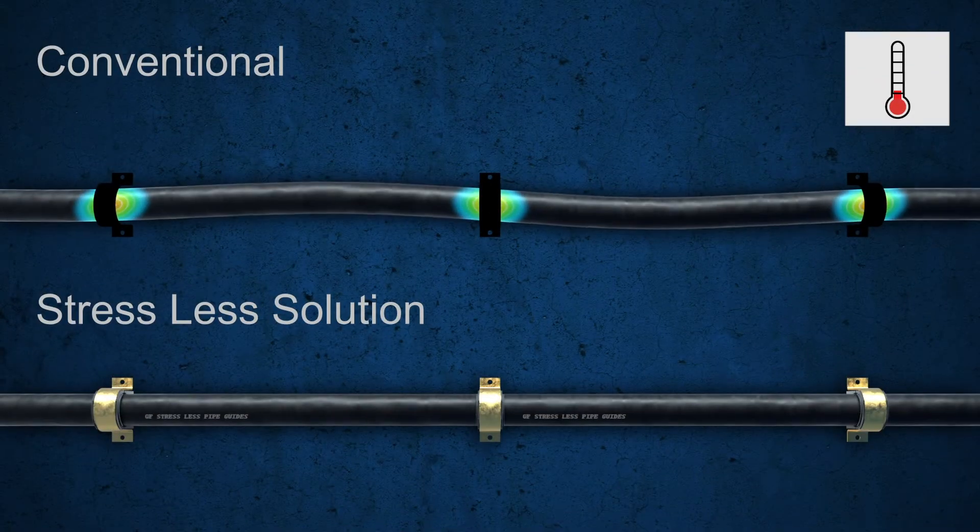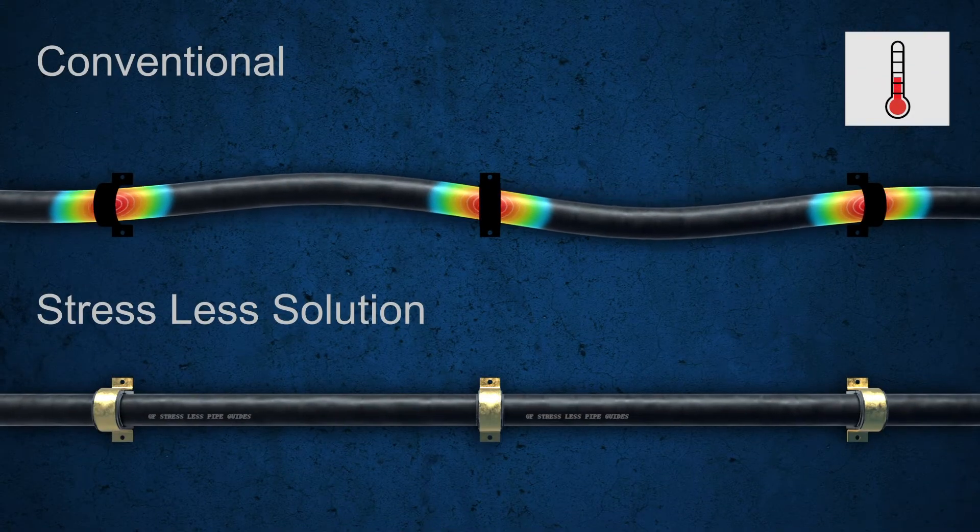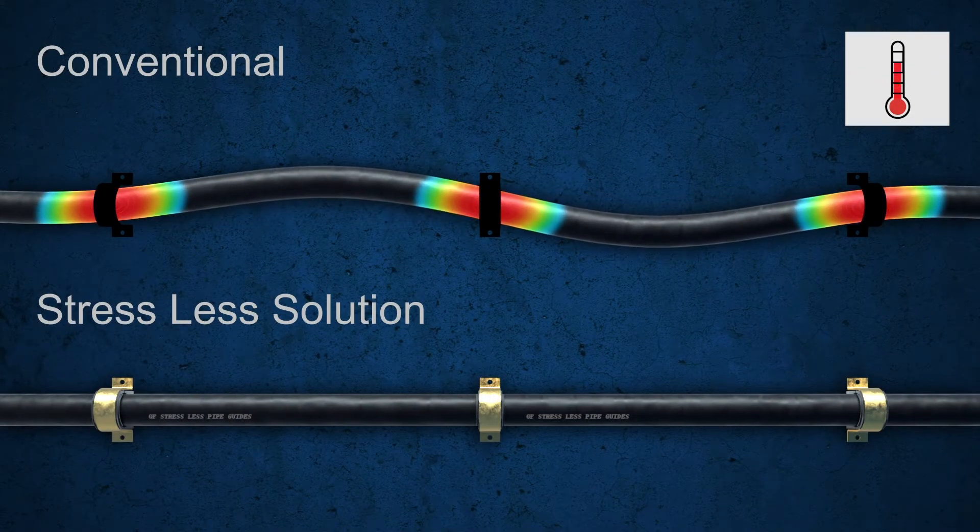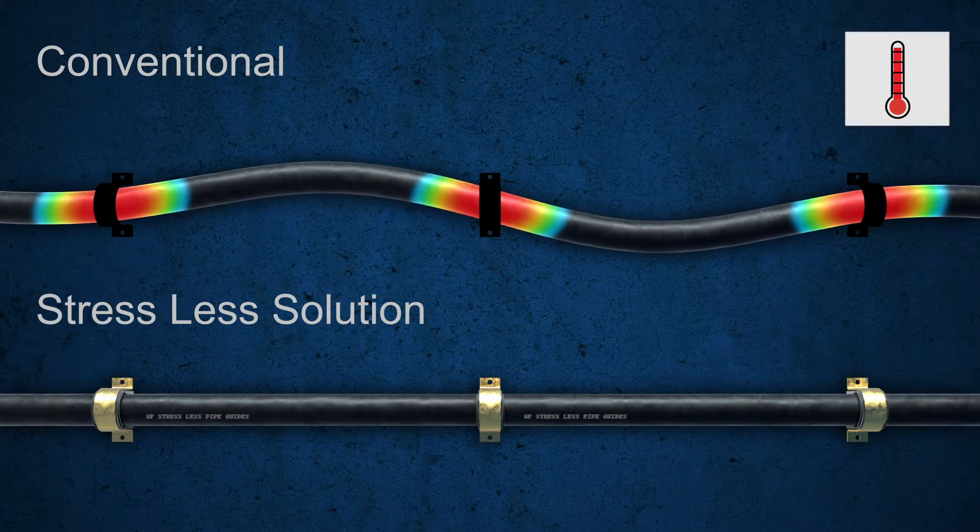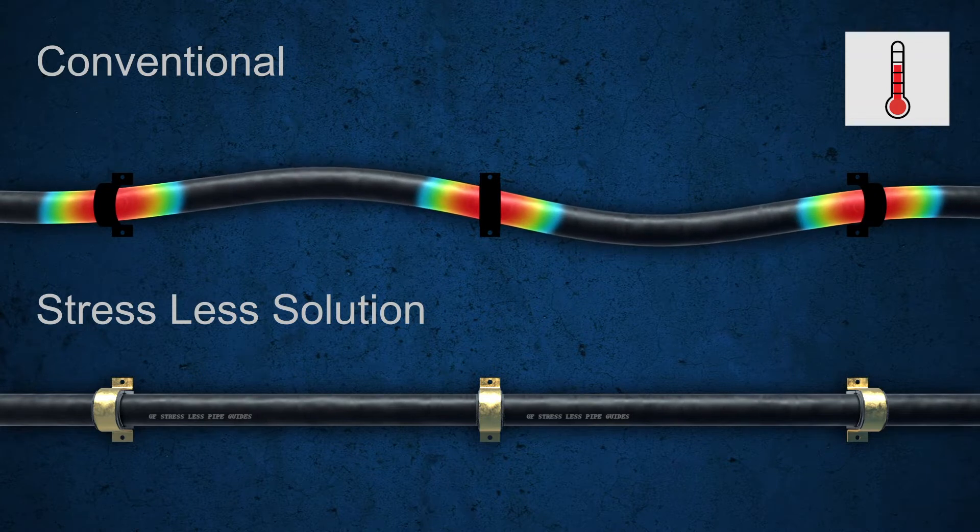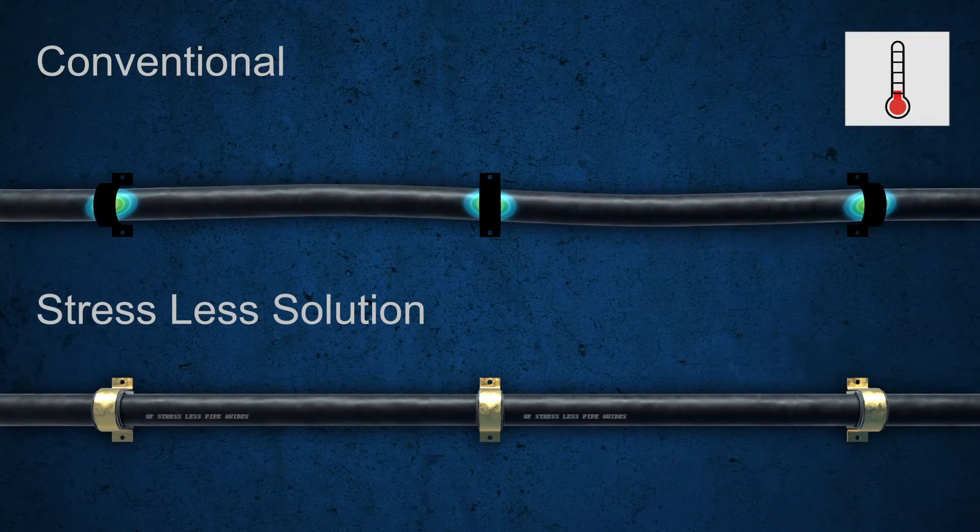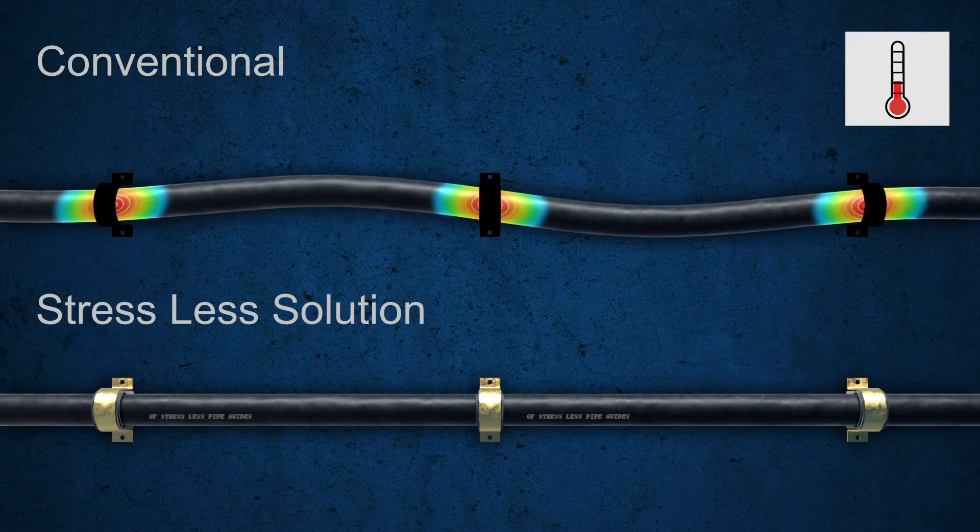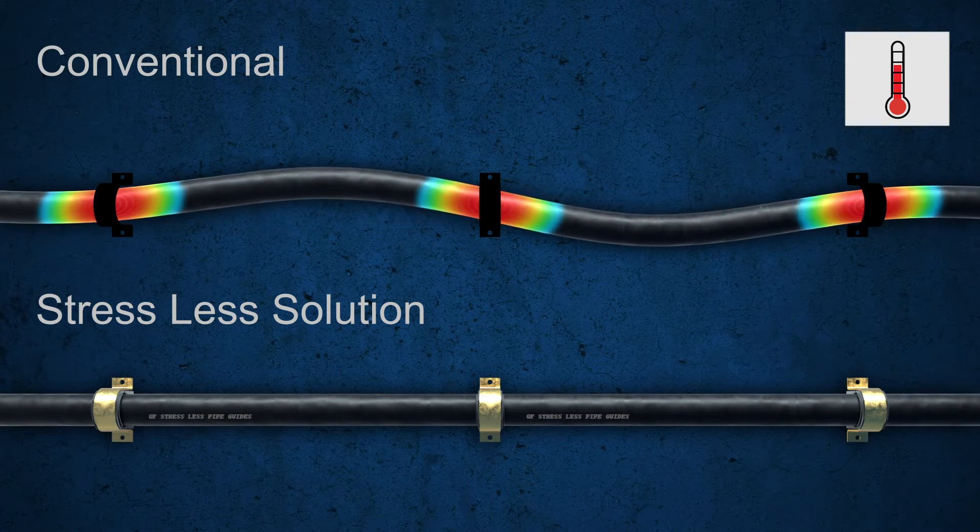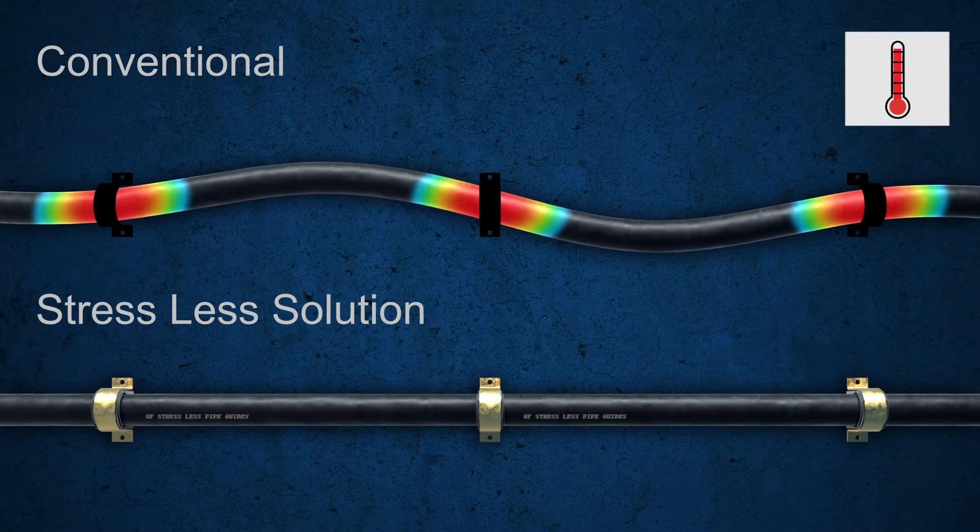Today's conventional pipe clamps are designed for metal piping. In operation, piping systems want to move due to thermal expansion and contraction. This is especially true for thermoplastics, which can expand and contract ten times more than metal. Traditional pipe clamps don't allow this, either by design or because of how they were installed. They often squeeze the pipe and don't allow natural movement.